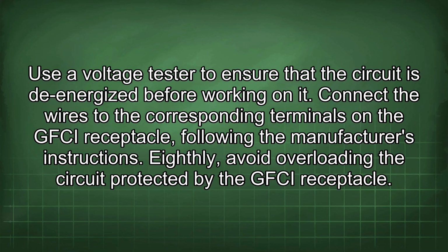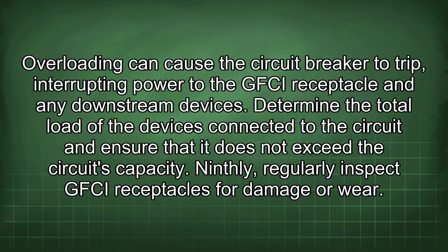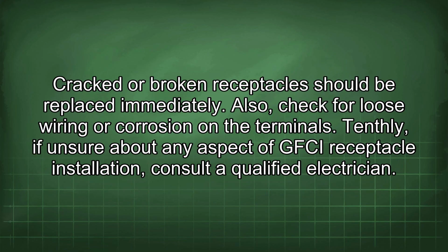Eighthly, avoid overloading the circuit protected by the GFCI receptacle. Overloading can cause the circuit breaker to trip, interrupting power to the GFCI receptacle and any downstream devices. Determine the total load of the devices connected to the circuit and ensure that it does not exceed the circuit's capacity. Ninthly, regularly inspect GFCI receptacles for damage or wear. Cracked or broken receptacles should be replaced immediately. Also, check for loose wiring or corrosion on the terminals.